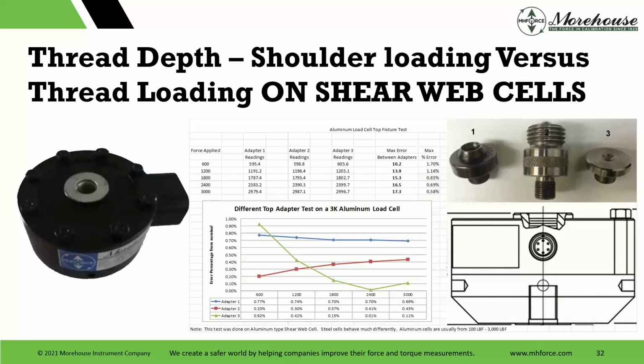Do you want a commercial cal with nonlinearity, hysteresis, SEB, or do you want it set up to be direct read with a conformity assessment? Do you want ISO 376? Do you want ASTM E74? Are you using adapters with it? How are you setting it up? Are you thread loading through the bottom? Are you loading it against the shoulder, or are you threading something into it? All these, I can go on and on.